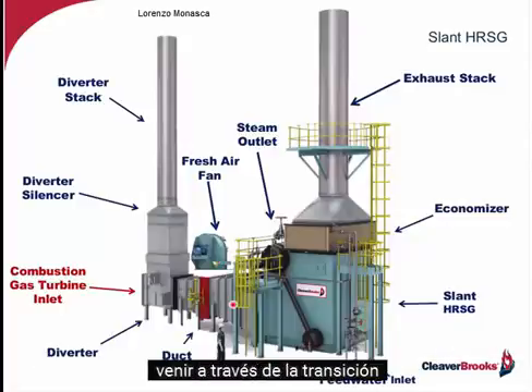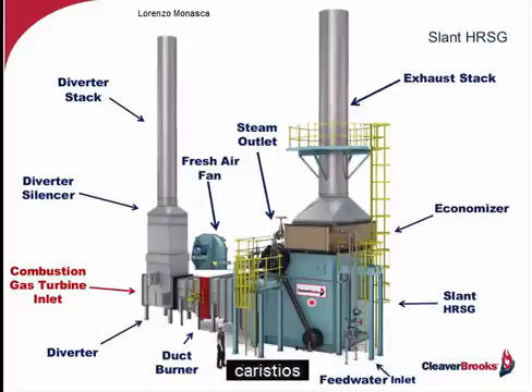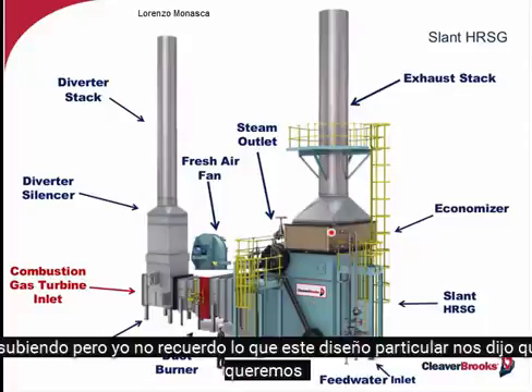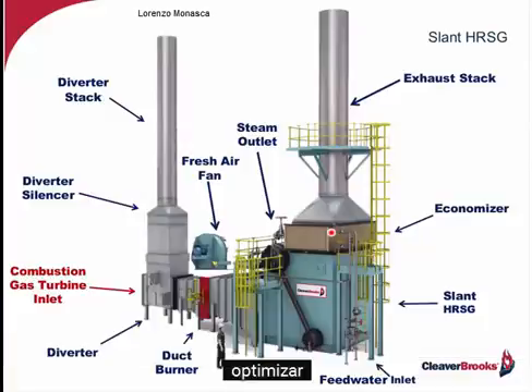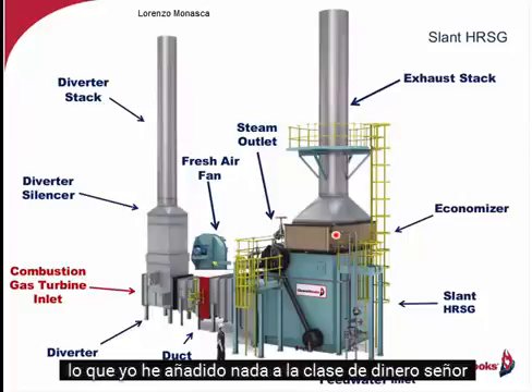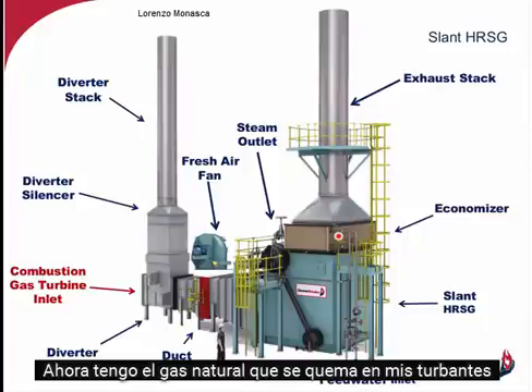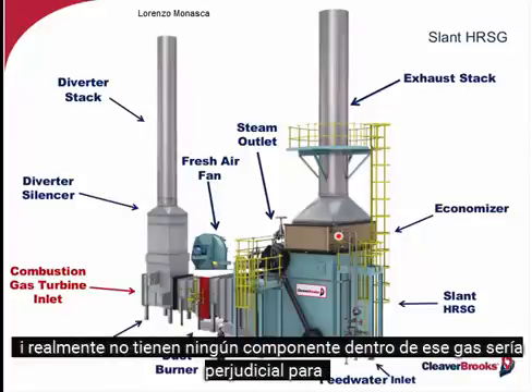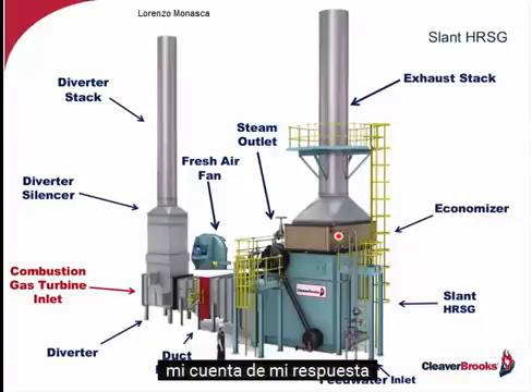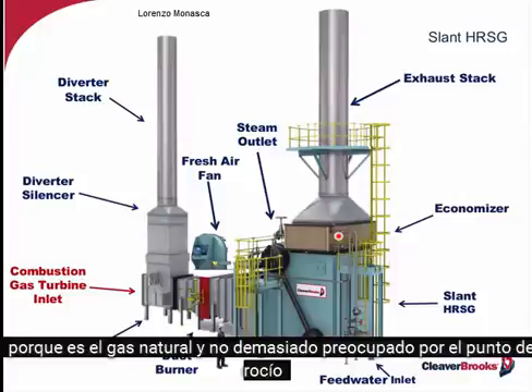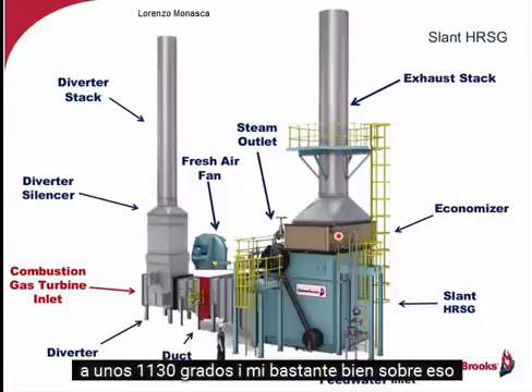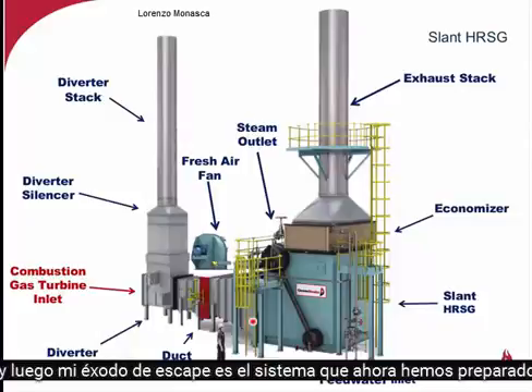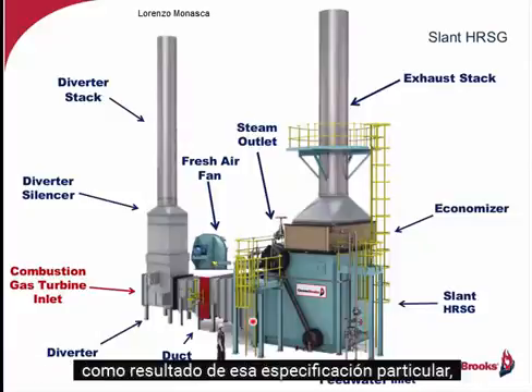I come through the transition, come into my HRSG, coming out of the top. Now remember, with this particular design, we said we wanted to optimize the overall efficiency. To do that, what I've added now is an economizer. Now, I've got natural gas being burned in my turbine. I don't really have any constituents within that gas that would be harmful to my economizer. Because it's natural gas, I'm not too concerned about the dew point. That's about 130 degrees. I'm operating well above that. And then my exhaust stack. So this is the system that we've now put together as a result of that particular specification.